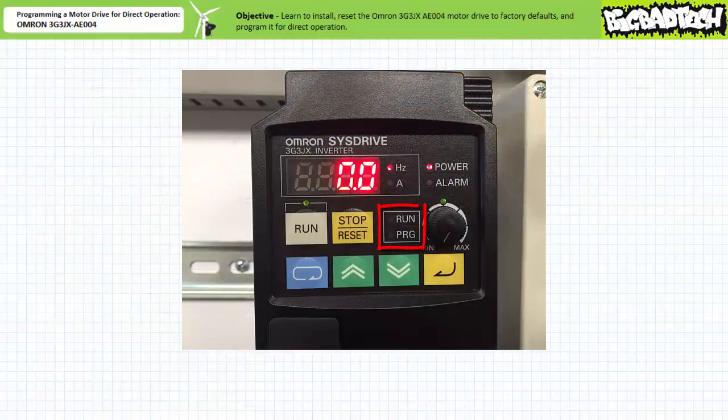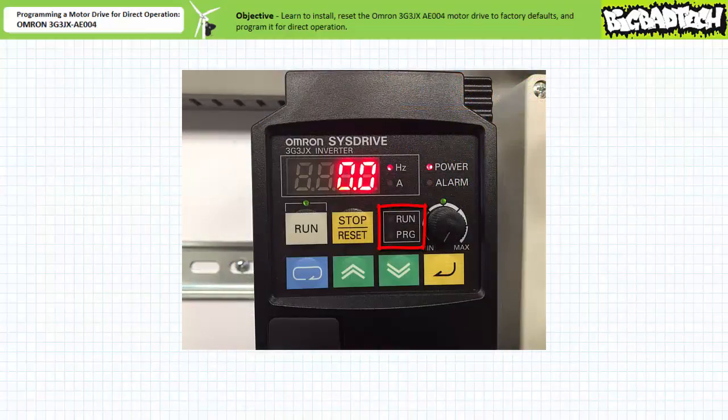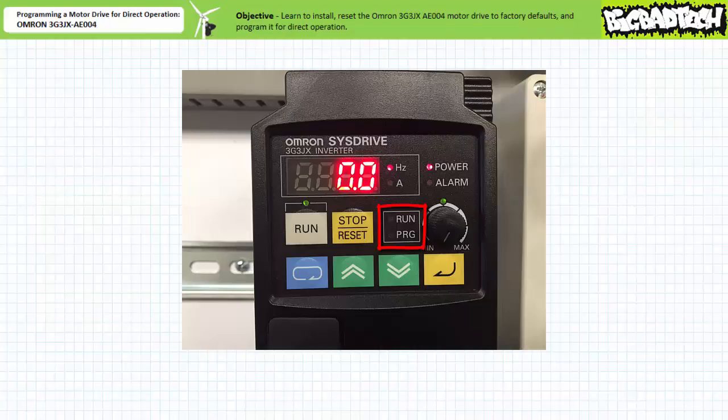The run LED is dark, indicating the motor drive is not actively accelerating, running, or decelerating a motor. The program LED is dark, indicating the parameters of the motor drive are not being actively programmed or changed. All seems well. Let's program this drive for direct manual operation.